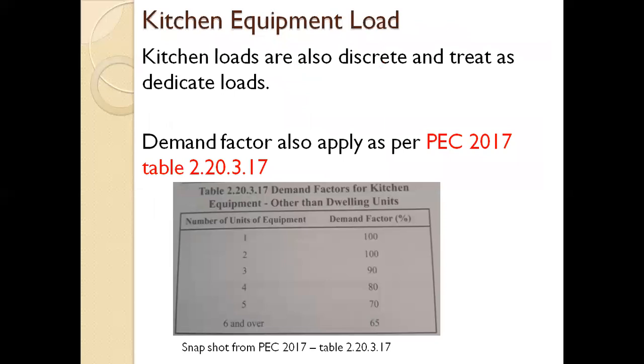Then, we have kitchen equipment. Only a few know how the demand factor is used for kitchen equipment. In PEC Table 2.20.3, this table is applicable to kitchen equipment other than dwelling units. For dwelling units, the application is different. So let us see. On the right side are the demand factors in terms of percentage.